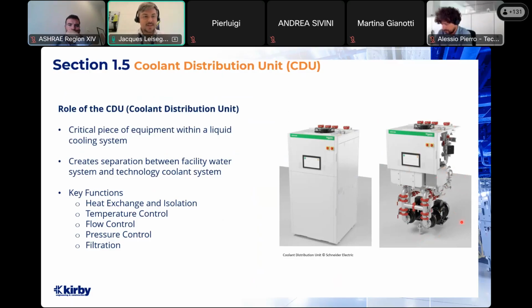There are control valves and sensors which ensure temperature control and temperature management, especially dew point temperature. You don't want the technology water loop falling below the dew point temperature. Finally, you have filtration. These CDUs typically come with 25 to 50 micron filters in them to filter out any contaminants or debris that might remain or come about in the technology cooling system. So that's the role of the CDU, and that's becoming a very critical piece of equipment within these systems.